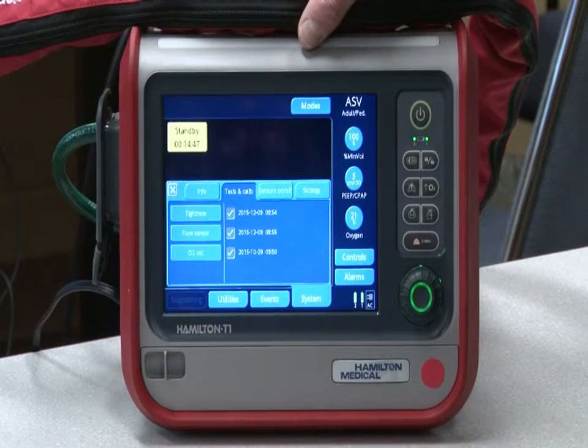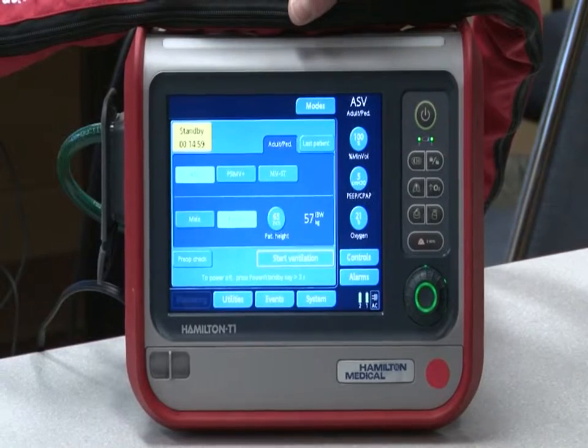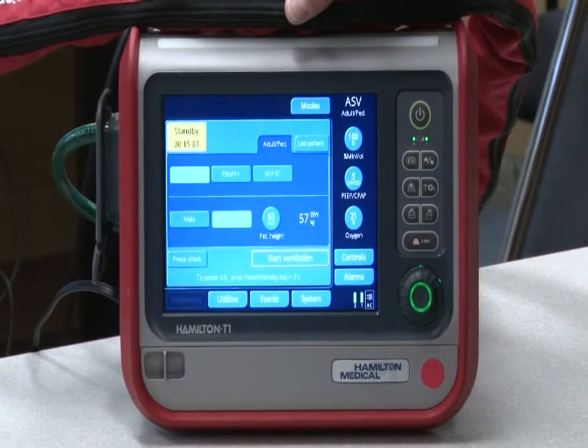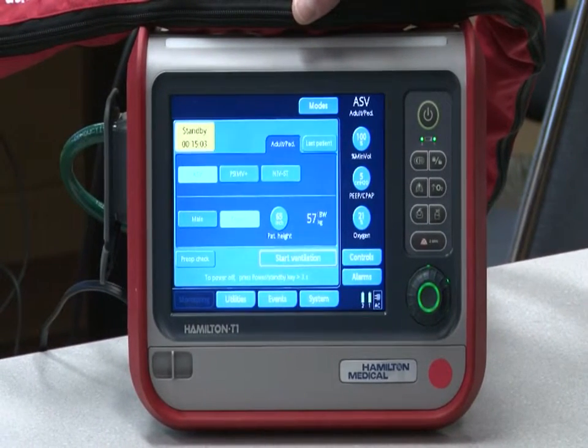Okay. So the first thing we're going to do, and I'll tell you in advance, so put the flow sensor on in the normal position, if you would. Yep. You can leave that adapter on, but just turn it around the normal way. Okay. The first thing we're going to do is the tightness test, and I'll warn you in advance when we hit that, it's going to take about 2 seconds, and you're going to hear a really loud noise. So be prepared for that.